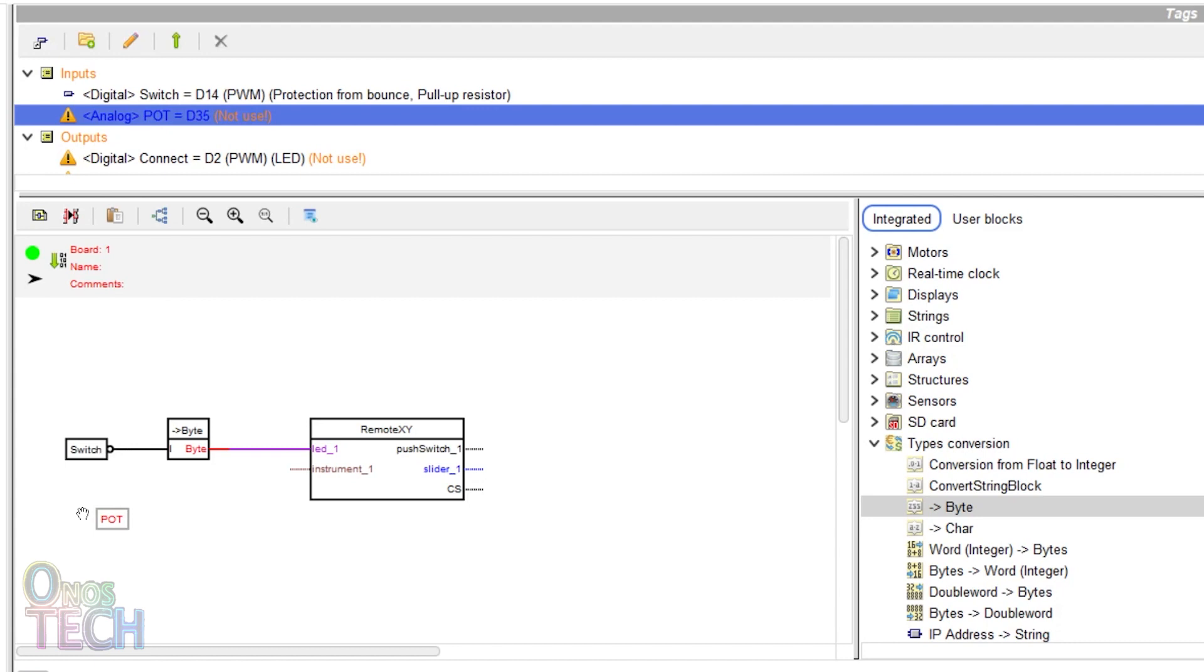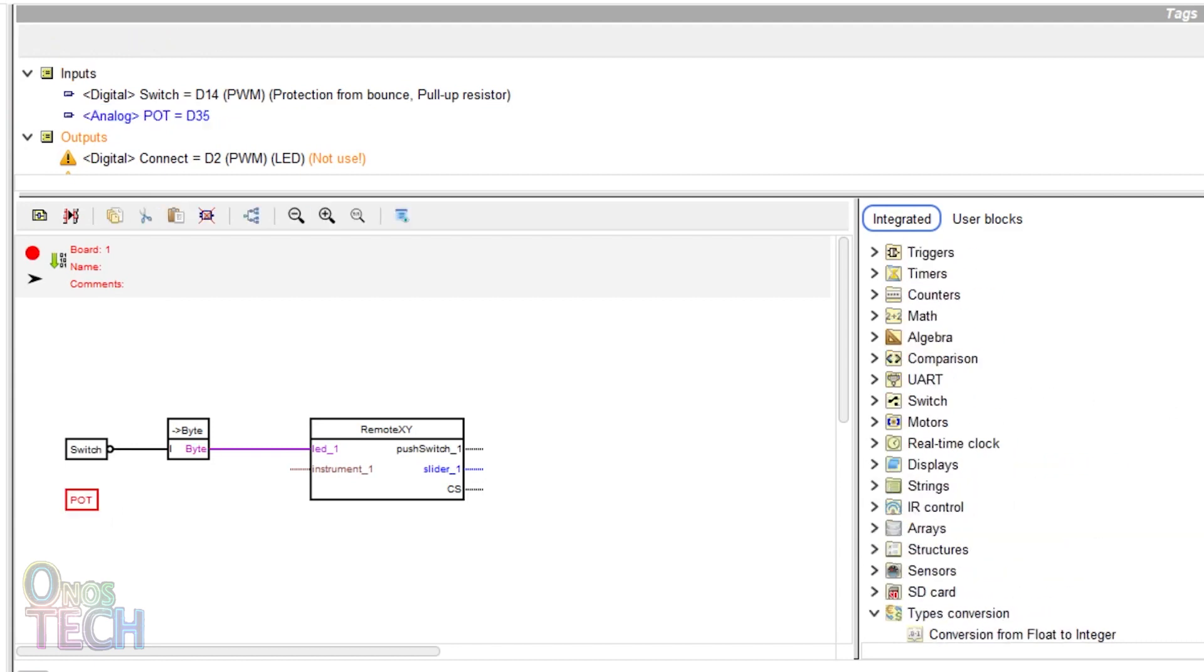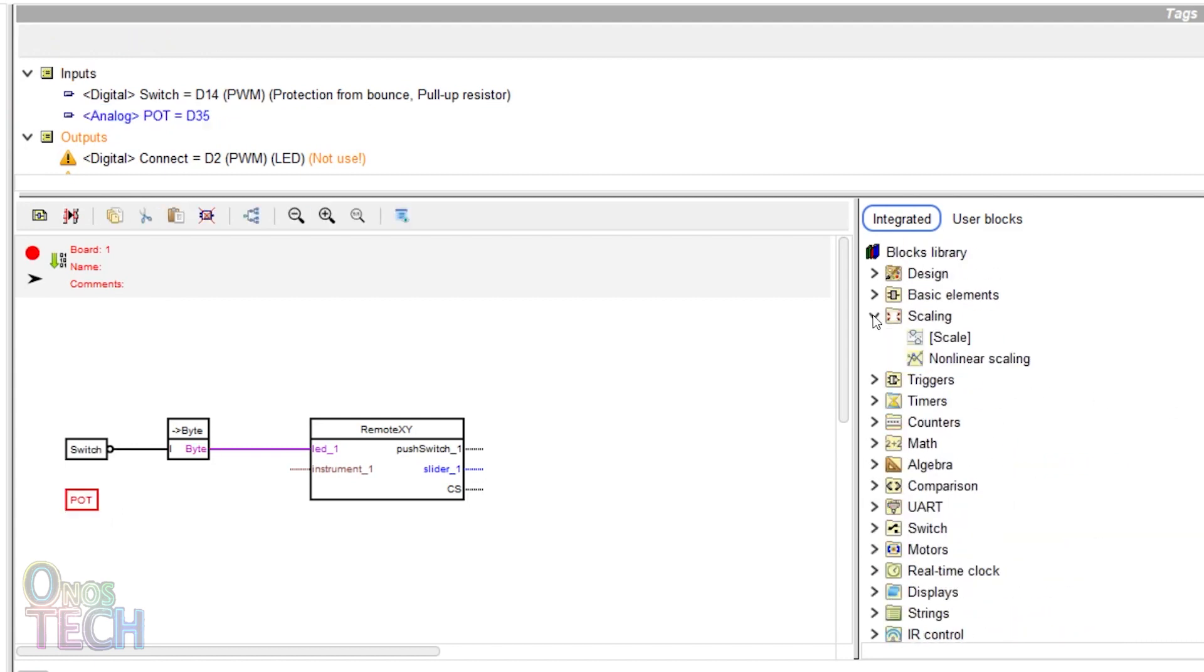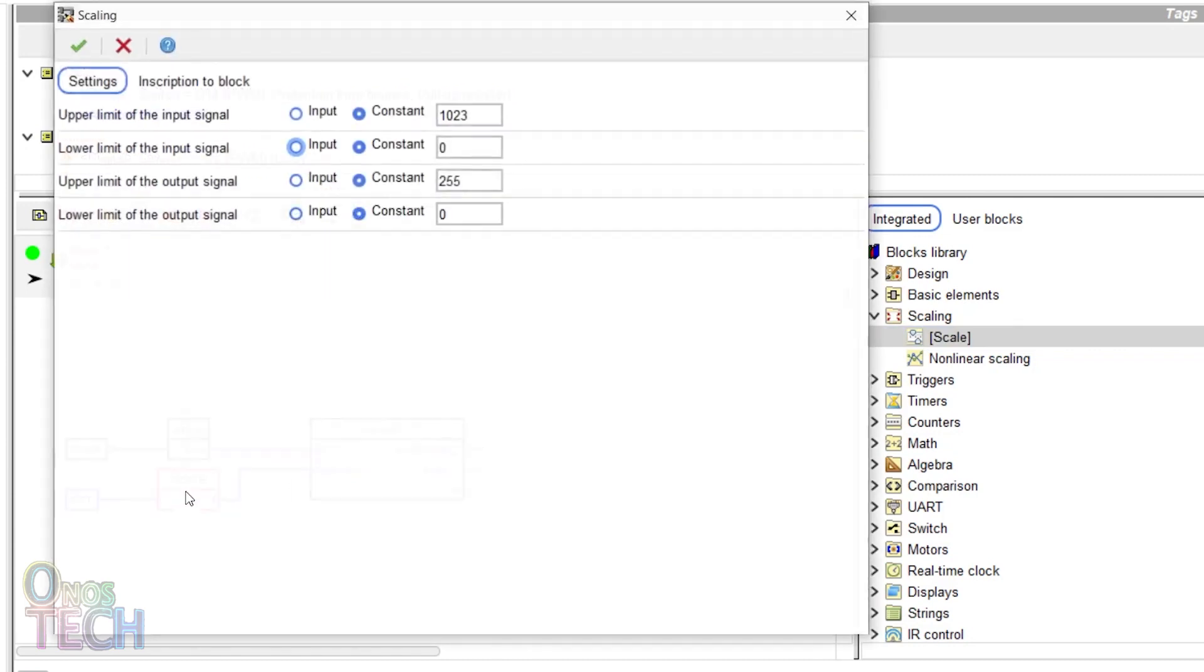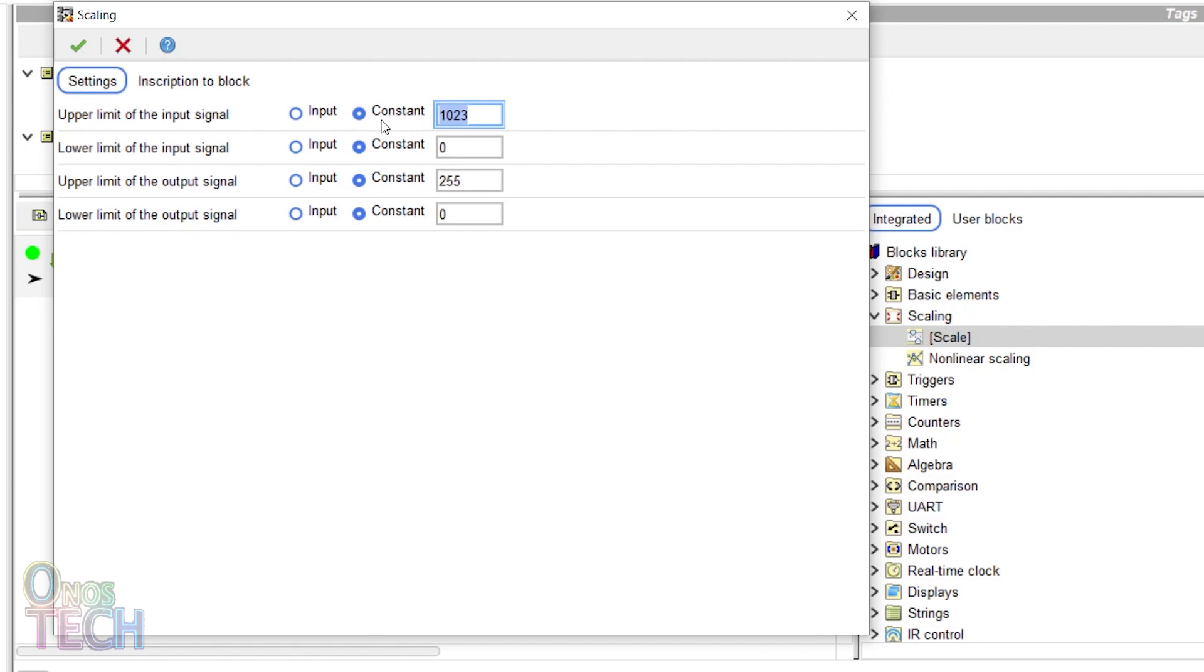Drag in the analog input and a scale block into the program and connect them to the block instrument input. Double-click on the scale block. Set the upper limit of the input signal to 4095 and the upper limit of the output signal to 100.